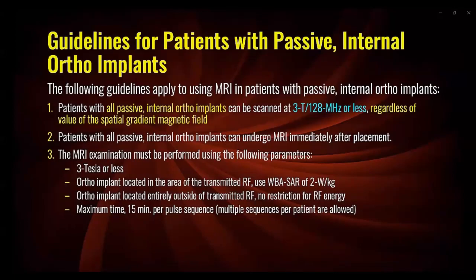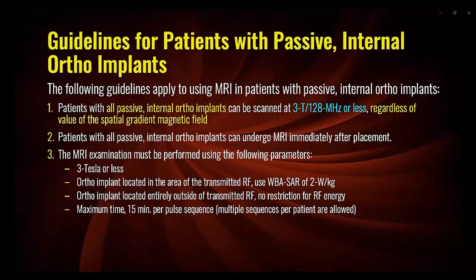For passive internal orthopedic implants located inside the area of transmitted RF energy, use a whole body average specific absorption rate of 2 watts per kilogram with the MR system in normal operating mode. For implants located entirely outside the transmitted RF field, there is no restriction on RF energy. The maximum imaging time is 15 minutes per pulse sequence, and multiple pulse sequences are allowed.